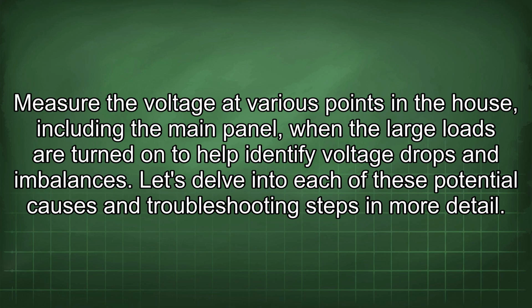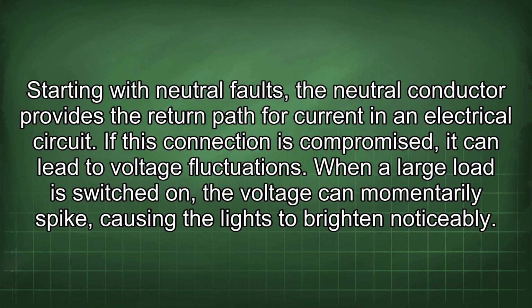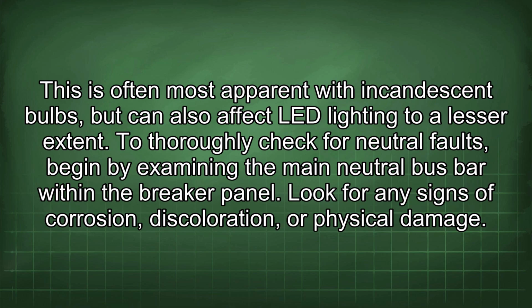Let's delve into each of these potential causes and troubleshooting steps in more detail. Starting with neutral faults, the neutral conductor provides the return path for current in an electrical circuit. If this connection is compromised, it can lead to voltage fluctuations. When a large load is switched on, the voltage can momentarily spike, causing the lights to brighten noticeably. This is often most apparent with incandescent bulbs, but can also affect LED lighting to a lesser extent.